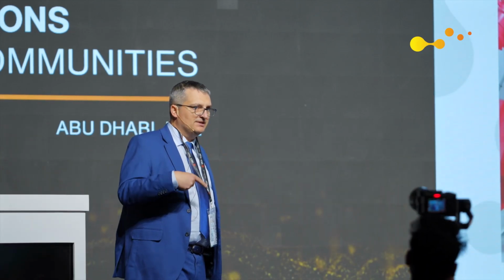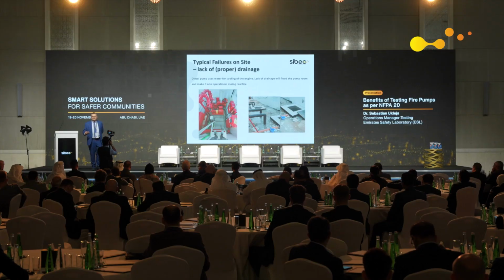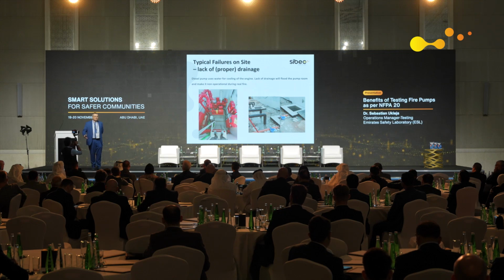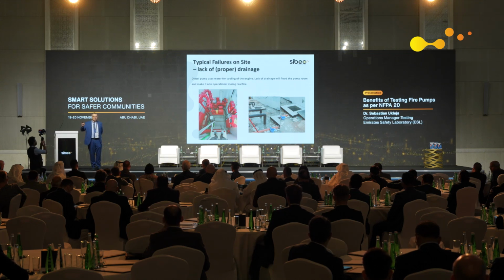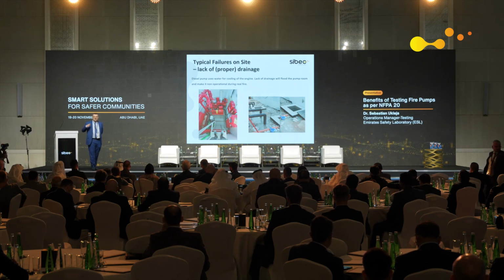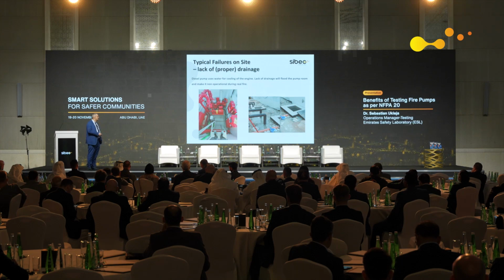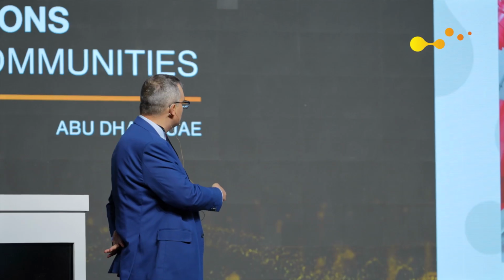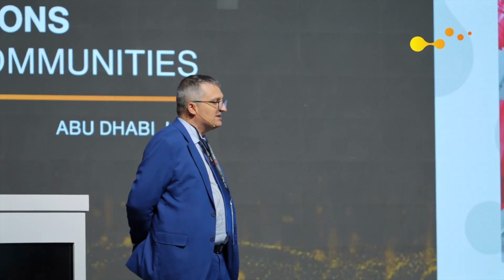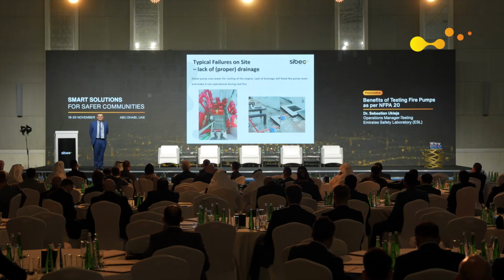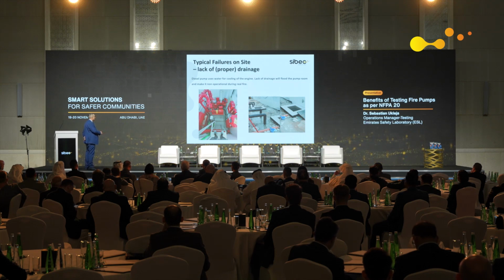So operation of the diesel pump leads to the situation that there is always water being discharged. I don't know if you use a motorboat or travel by motorboat somewhere, always the engine at the back discharges the water, which is the cooling water. So imagine how long this pump room can operate on the diesel pump if the water is collecting inside. And again, this is not the problem of the pump. The problem is of the installation.